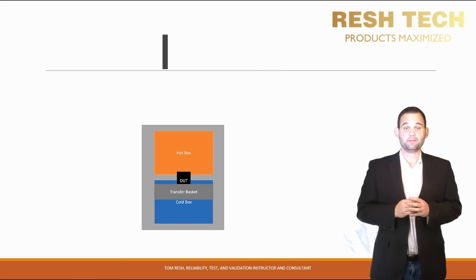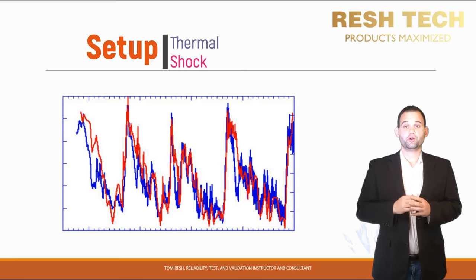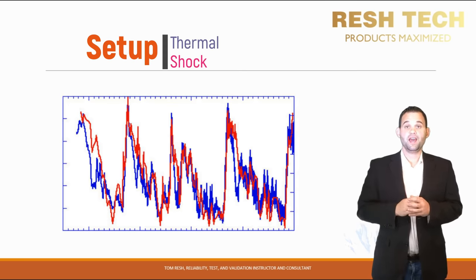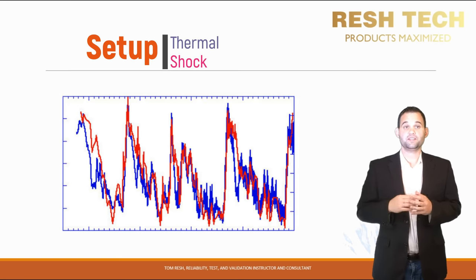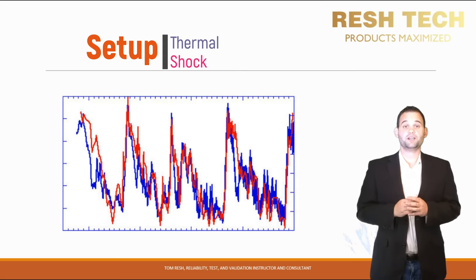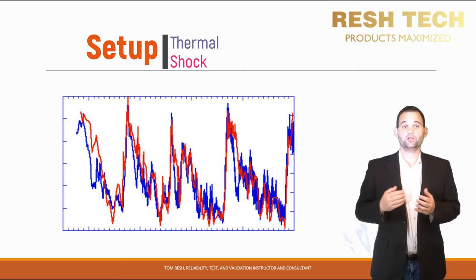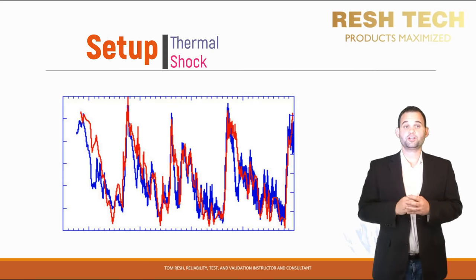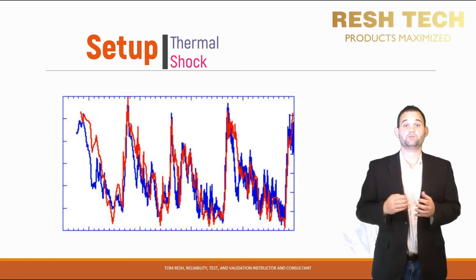Let's jump into setup and planning for thermal shock. First, we will cover temperature set points. The ideal approach is to understand your product's worst-case temperature environments, frequency of temperatures, and the diurnal cycle for the environment your system will be installed in or operated in. You can use these cases to create temperatures or even apply an acceleration factor to expedite stresses and identify potential failure modes. If you are not sure or need a quick solution for what temperature to test, refer to an industry-specific specification for your system or product, which will have guidelines on temperatures and cycles to use.